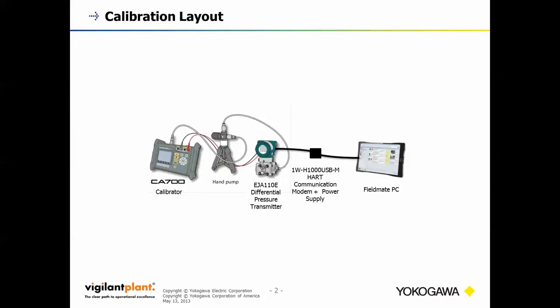So here is your typical calibration layout for a pressure transmitter. We've got a calibrator here, the CA700 from Yokogawa. It's more accurate than the pressure transmitter we're calibrating, so that's a necessity. It's a 0.01% of reading accuracy, where the pressure transmitter we're calibrating is a 0.055% of span transmitter.